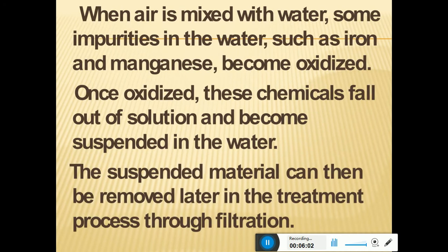So whenever the air is mixed with the water, some impurities in the water such as iron and manganese will also be oxidized, okay. Once oxidized, these chemicals fall out of solution and become suspended in the water, okay. And the suspended materials can then be removed in the later treatment processes, that is by adding coagulants, and we do a process called sedimentation and all, and also in the process of filtration.